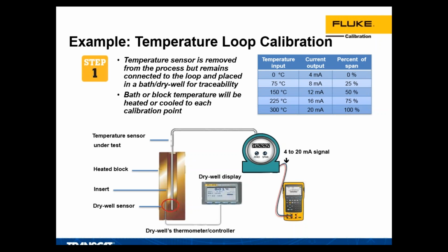So I might go through 0 degrees Celsius and 75 and 150, etc. And then the current output, you can kind of see in the second column on that blue table up there, would be some milliamp output that would be read by the 754. It would keep track of the temperature reading from the dry block and the output from the 754. So that's the concept here.